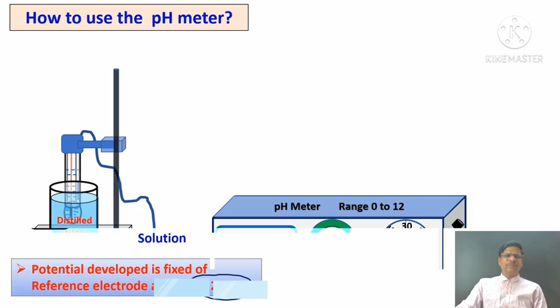Now, how to operate and use the pH meter. Before using the combined glass electrode for pH determination, what do we have to do? We must place the combined glass electrode in distilled water for 24 hours. That gives rise to the formation of a thin layer of water on the glass membrane, which acts as a semi-permeable membrane to exchange Na+ ions and H+ ions with each other. This is the purpose. This is called activation of the glass electrode. If you have not done the activation of the glass electrode, the pH sensed by the glass electrode or the pH sensor will not be accurate.